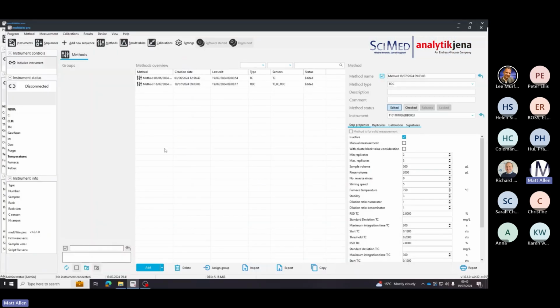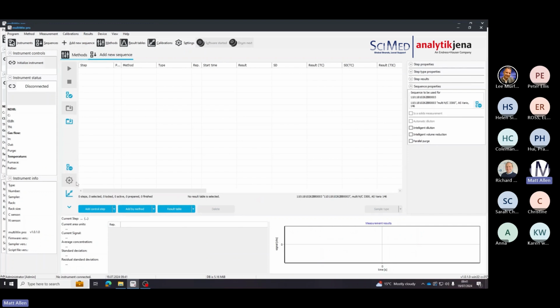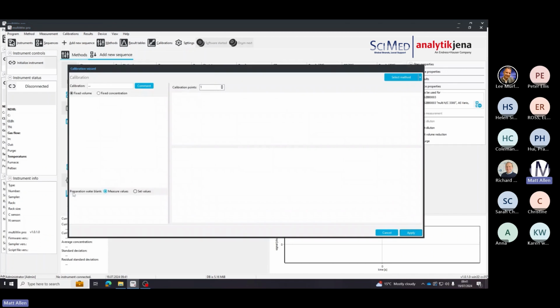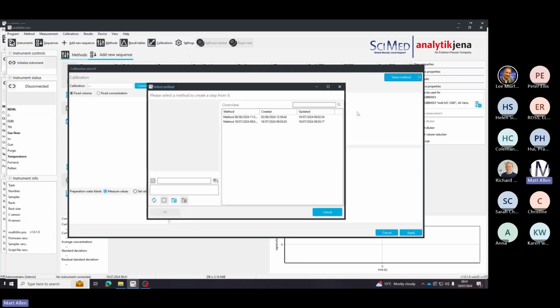Okay, so we're now ready to set up a calibration, and similar to running a sequence, we go to add new sequence, and you can see just this little icon here is the calibration build wizard. So we click on this. This opens the calibration wizard, and straight away we've got a choice of fixed volume, fixed concentration. We've got the calibration points, and we've got this button on the top right, select method. Which method do we want to use to set up this calibration? So we're going to use this previously set up TC method.